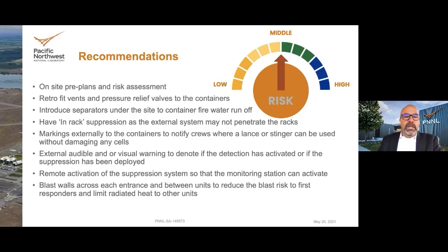External audible or visual warning to let you know what's triggered or activated—that's a great point. Remote activation of the suppression system, so the monitoring station can activate it—it really should be automatic. Someone remote doesn't have eyes on the situation, so I'm not sure that would support remote activation. And then blast walls across each entrance to reduce the blast risk. This is definitely a viable option when you have a siting issue next to other critical facilities.